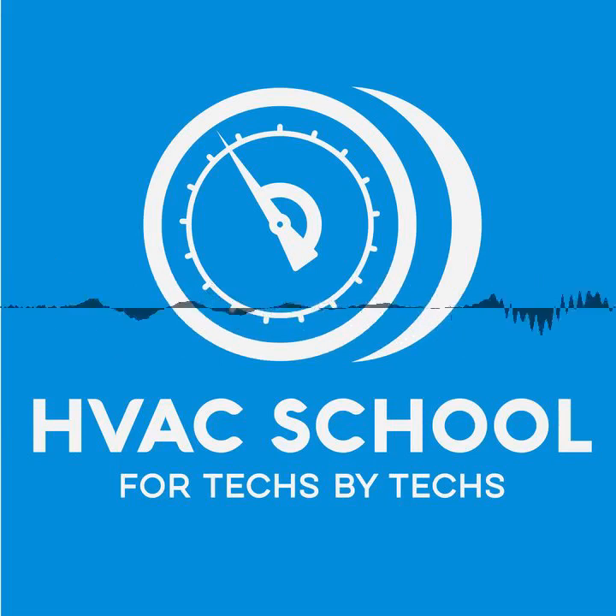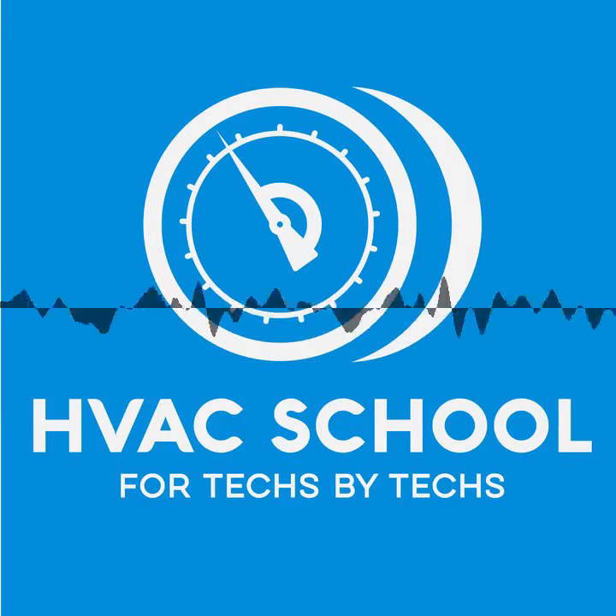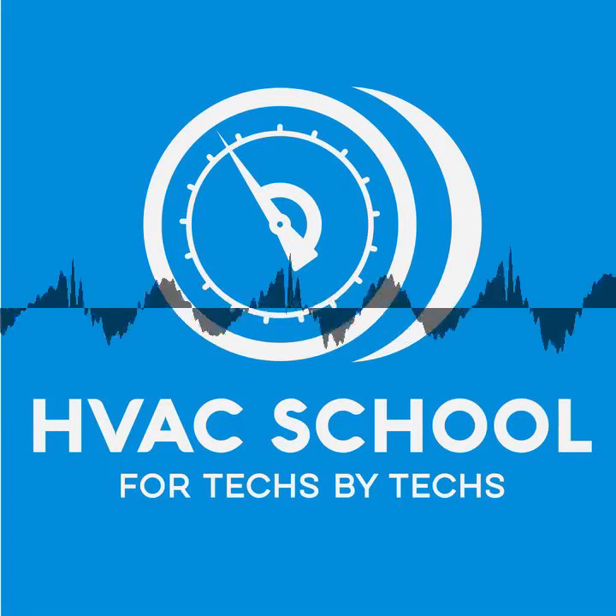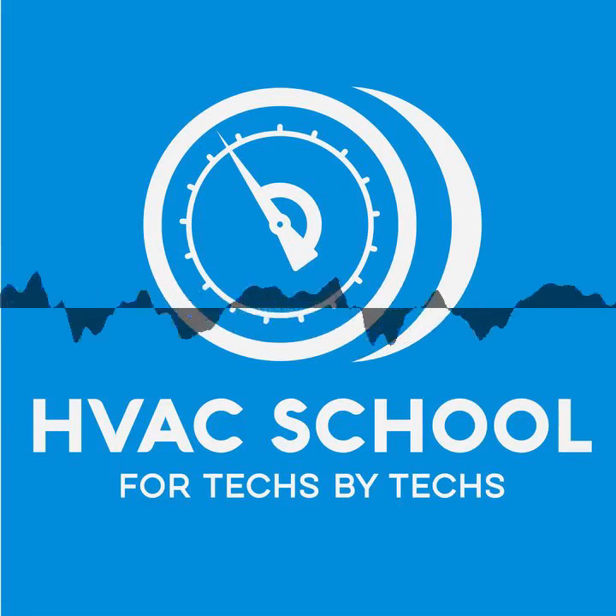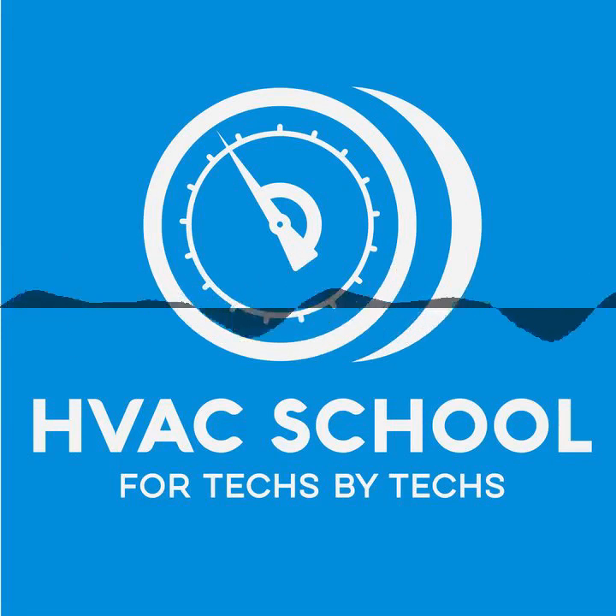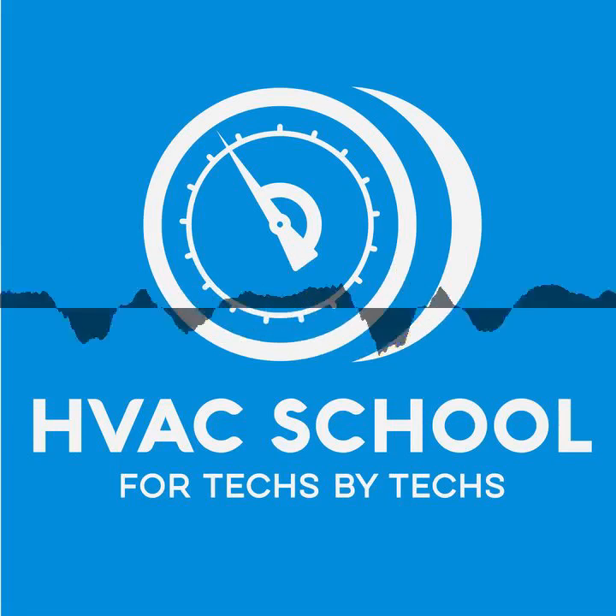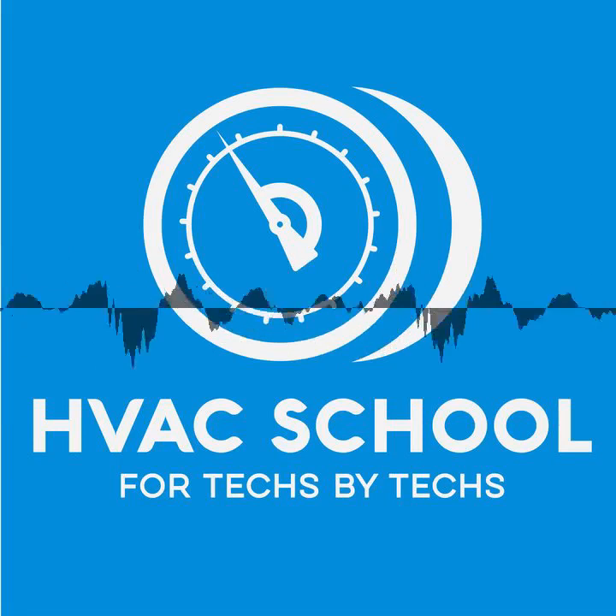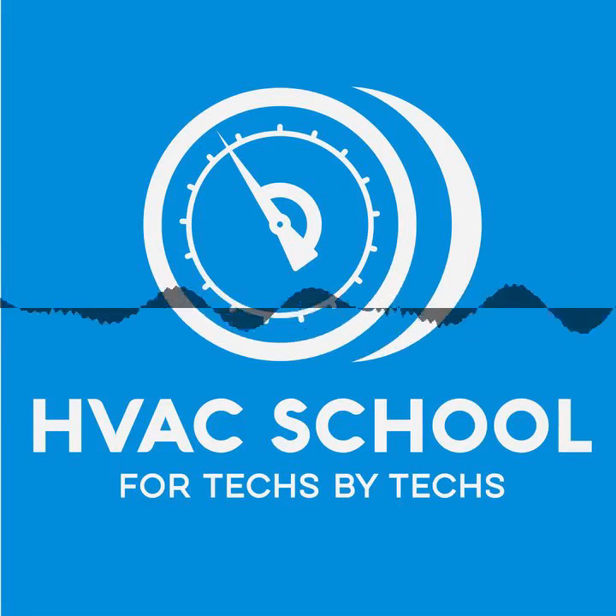Historically, in fact, not just historically, currently, we're relying on that dry bulb indication to bring the system on and run it long enough to do the dehumidification. So the dehumidification is kind of just along for the ride. It's never really been a focus. So if you take your region down there, you tailor the system so that it operates with much lower evaporator temperatures. So you have a latent focus compared to, say, up in the north, central, west, where you may have really hot days, but you only have probably half the humidity in the air that you have where you're located. So they would run a much higher evaporator temperature.